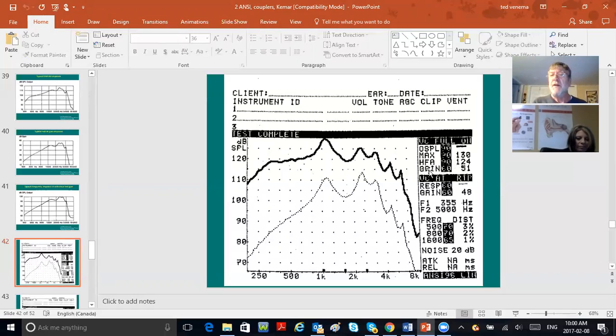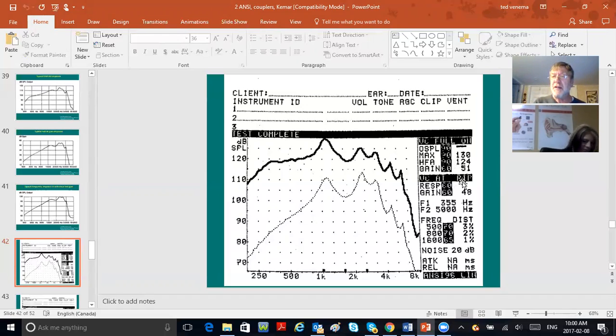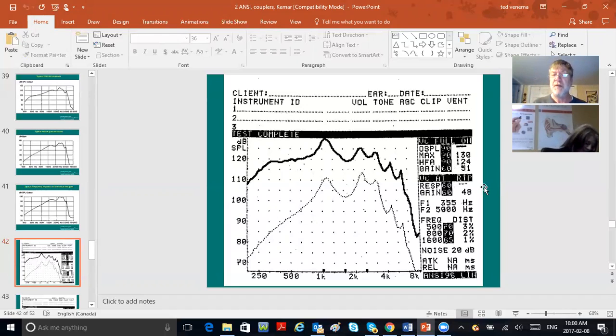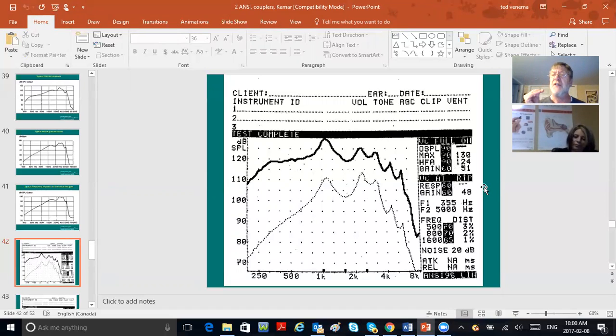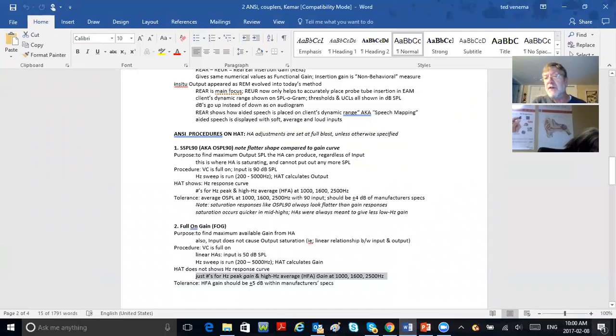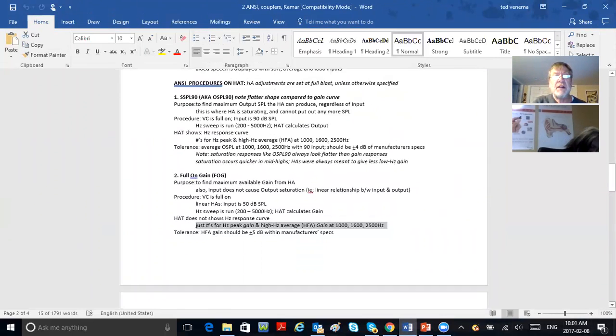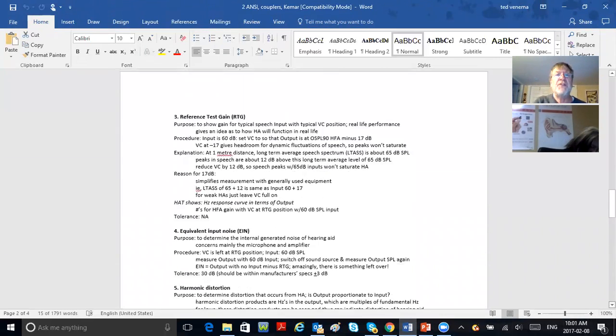We go to the third measurement: reference test gain, also called VC at RTP—reference test position—which means your volume control is reduced from full blast down to less. Let's read about it.